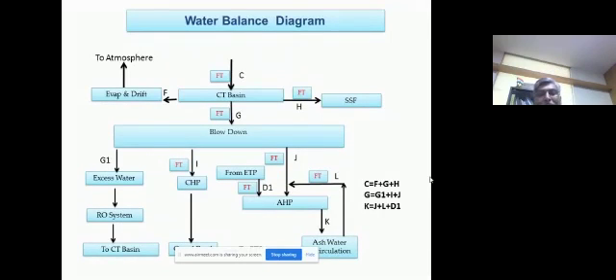Then see the overall picture, that is C is F plus G plus H, and G is G1 plus I plus J, and K is going to be J, L, D1. So it is a very, very closed system, except drift and evaporation loss, the entire thing is trapped. So excess water is going to the RO system, and from there it is coming back to recycle to the cooling tower basin.